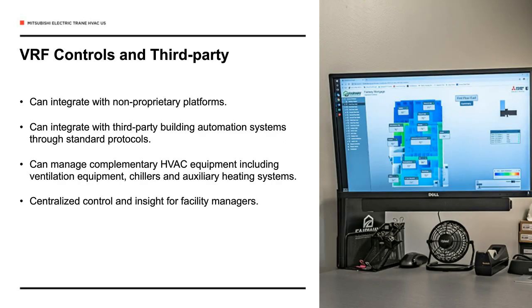VRF control software can integrate with non-proprietary platforms such as Tridium's Niagara 4 framework for advanced sequences and higher-level building automation systems control. VRF controls can integrate with third-party systems through standard protocols like BACnet or Modbus. This allows for centralized control and even more insight for facility managers.